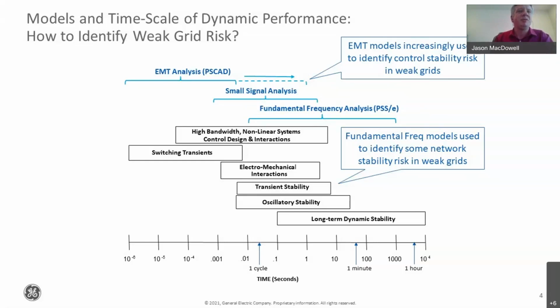But more control stability that we talk about related to inverter-based resources, as Nick pointed out, needs to be assessed with more detailed models, electromagnetic transient models like EMT. And more today, to understand the capability of the equipment and what might go wrong, EMT models are being used more and more. The other trend is that they're being used for longer time durations as well, to look at the many hierarchies of control that need to coordinate and be interoperable with one another.